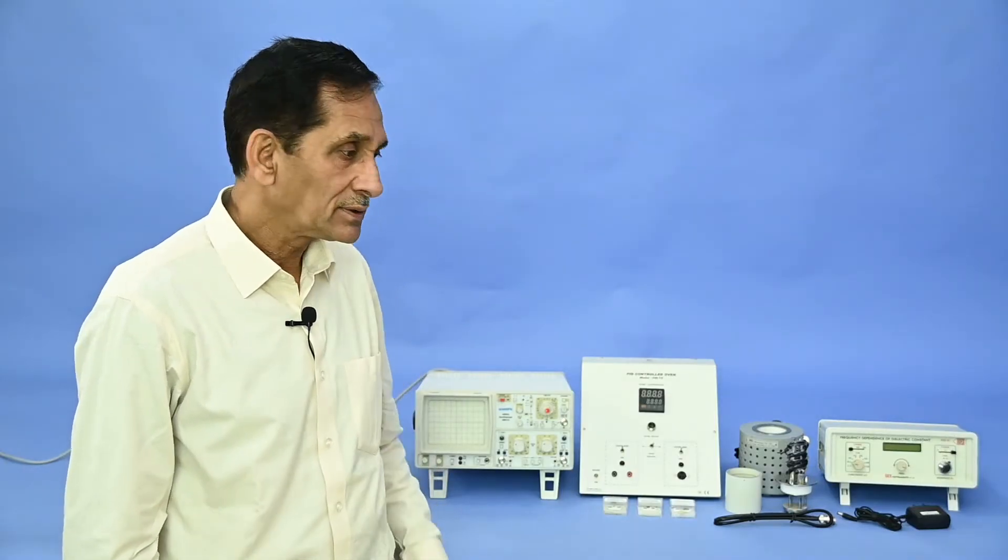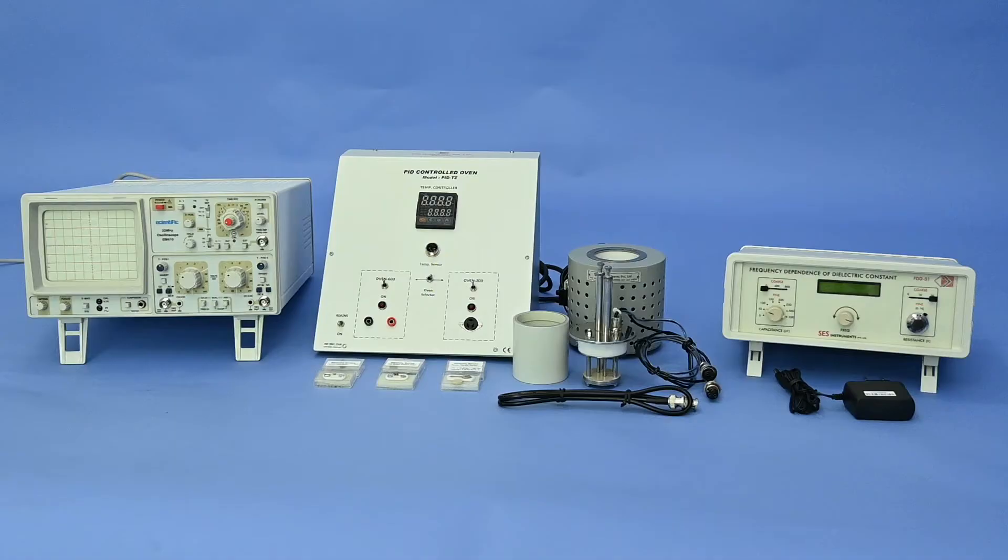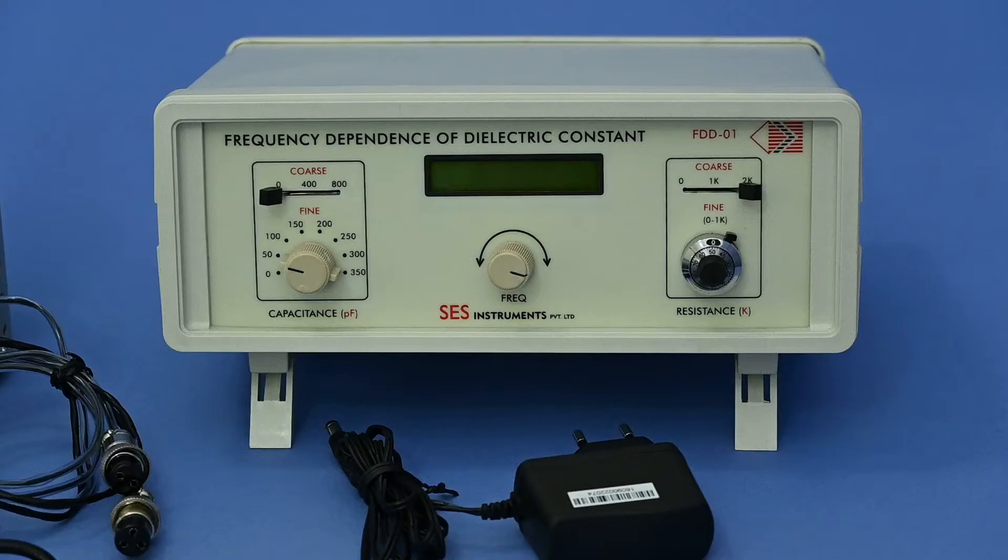When you open the carton, you will get the different parts of the instrument. Main unit of study of frequency-dependent dielectric constant, model FDD01, consists of built-in sine wave oscillator with frequency range 1 kHz to 20 MHz, but experiment used only from 1 kHz to 50 kHz.